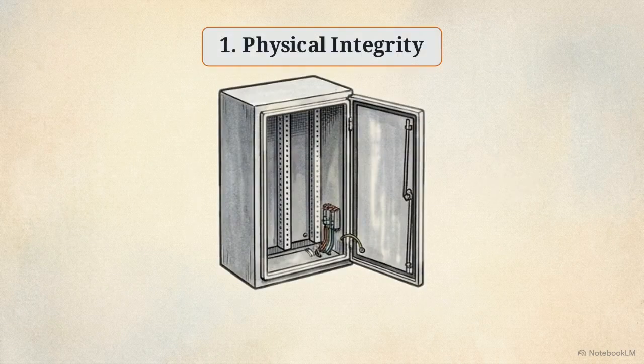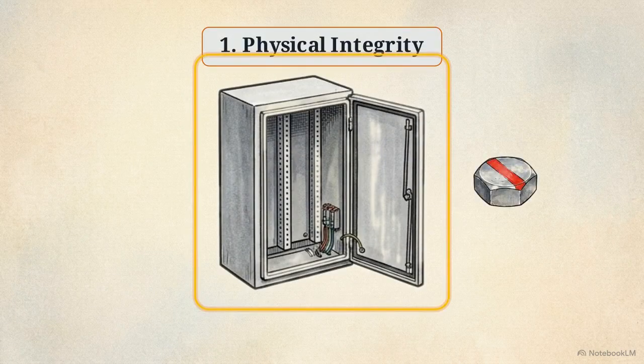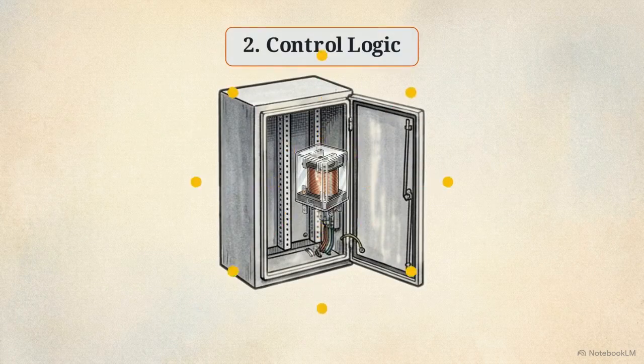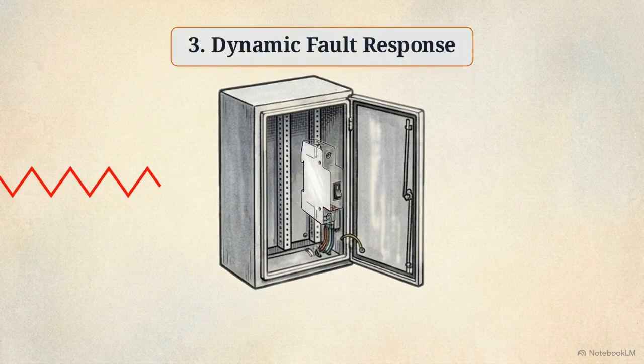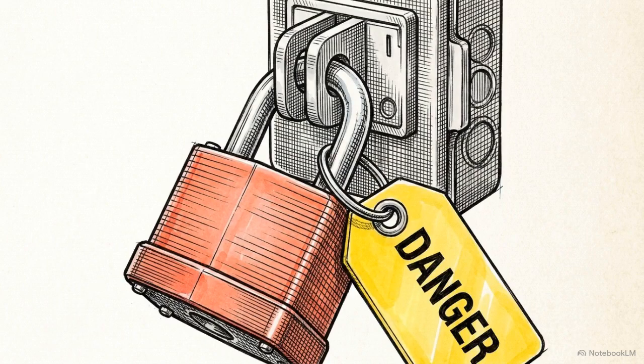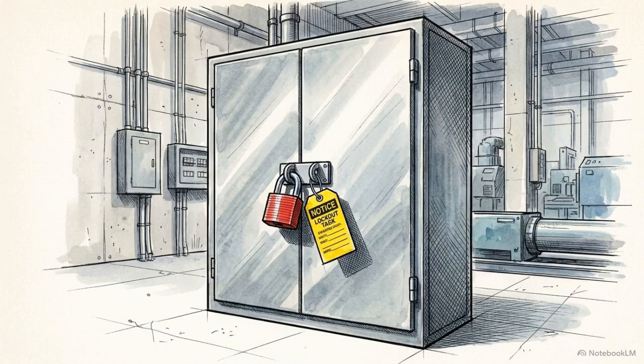The commissioning protocol operates through a threefold validation matrix. We test the panel's physical integrity, its internal control logic, and its dynamic response to simulated faults. Before the panel is opened, technicians implement a strict lockout-tagout, or LOTO, procedure. This physically prevents anyone from energizing the board during the testing phase.